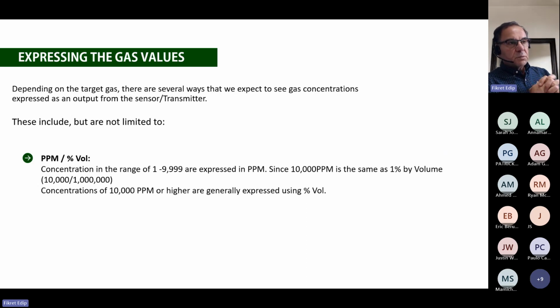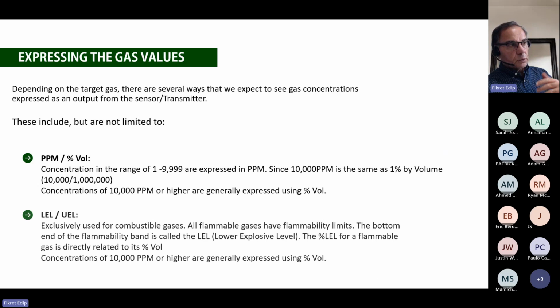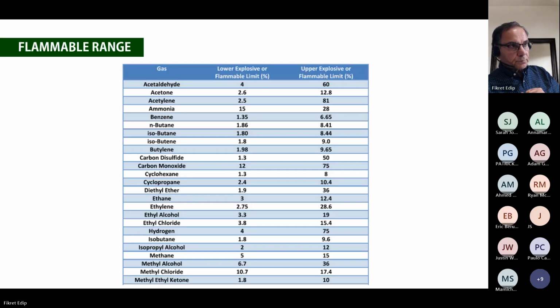And this is typically used when we are measuring CO2, for instance, in greenhouse applications. You say, I need a sensor, it's 5% volume. A 5% volume sensor equates to 50,000 ppm of CO2. But this is just an expression value, and you also need to know it when you are ordering your calibration gases, etc. The LEL and UEL, lower explosion limit and upper explosion limit, are also typically used for flammable gases to detect the flammability rate for that gas.